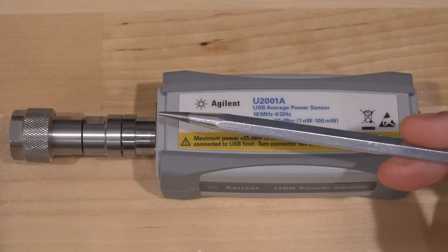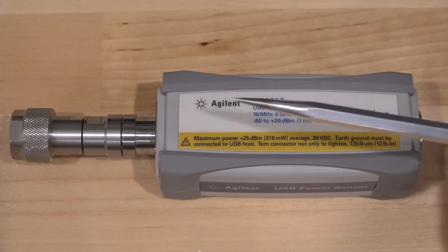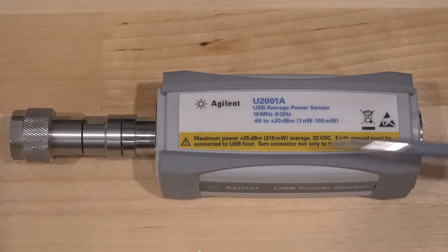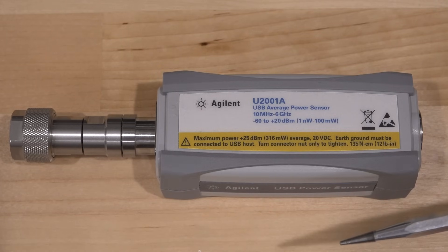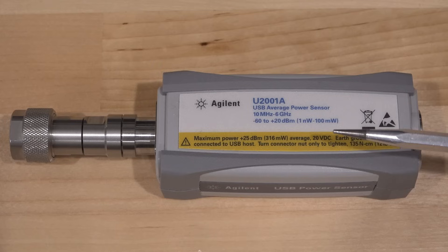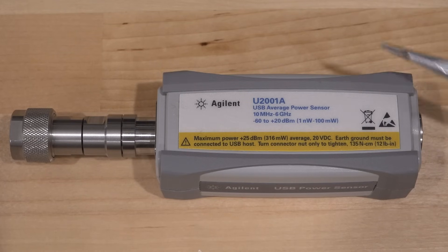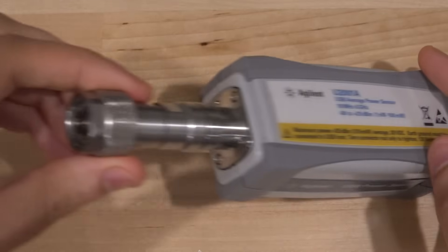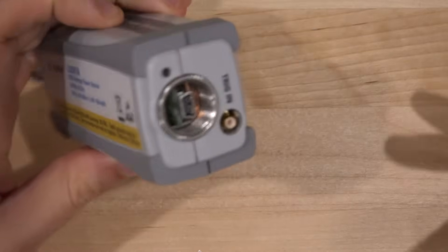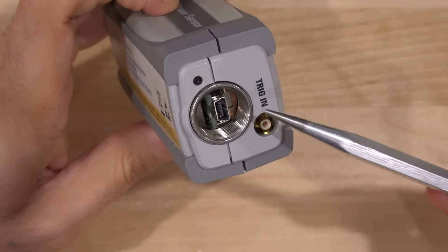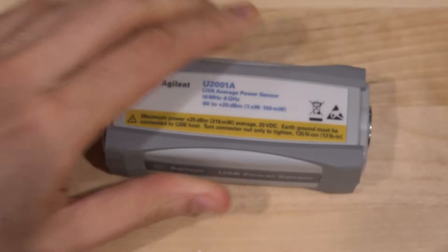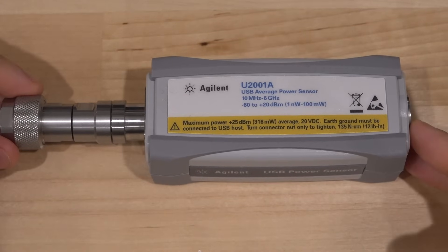Basically the main detector is damaged, probably by putting too much power into it, more than 20 dBm. The damage level is like 25 dBm. We're going to take it apart and see how it works, especially because this is a fully enclosed unit. Unlike other power sensors that require a power meter, this is all encompassing. It's got a Type N connector in the front and a mini USB port with a screw terminal and special cable.